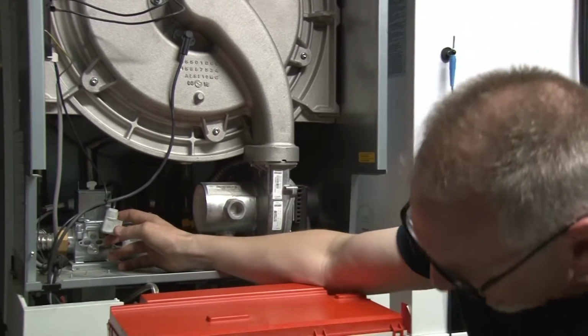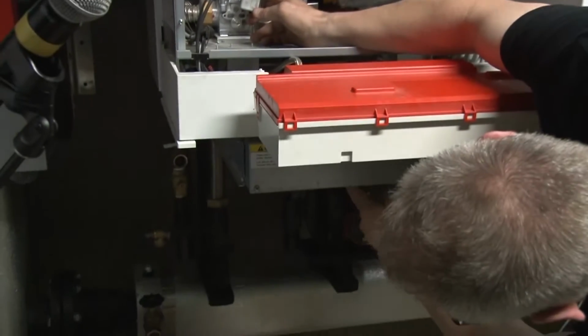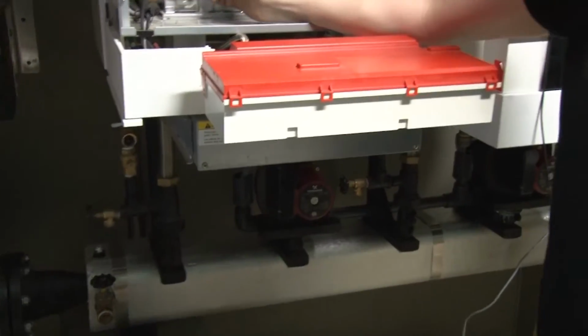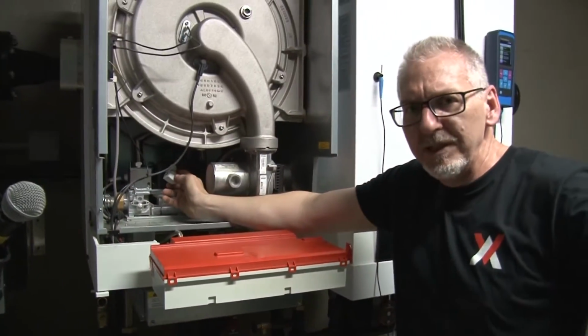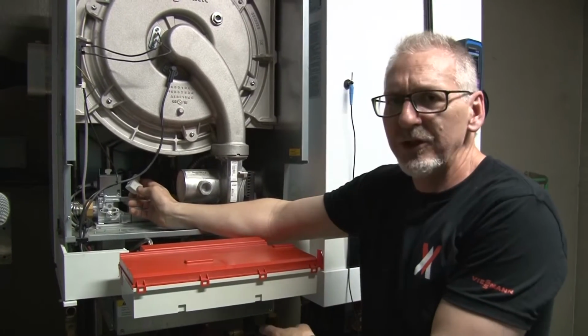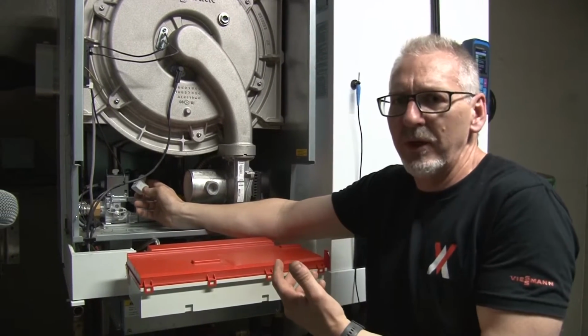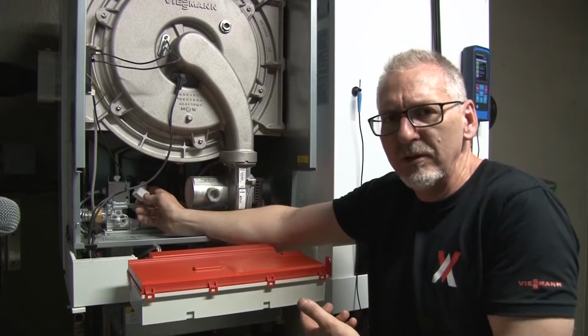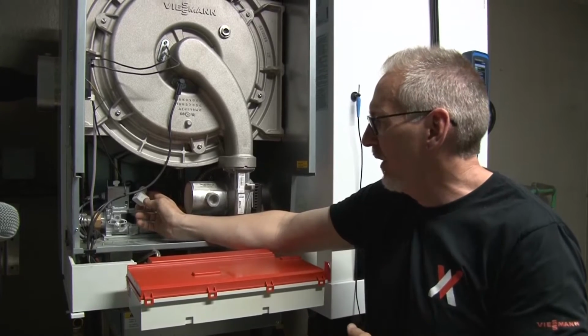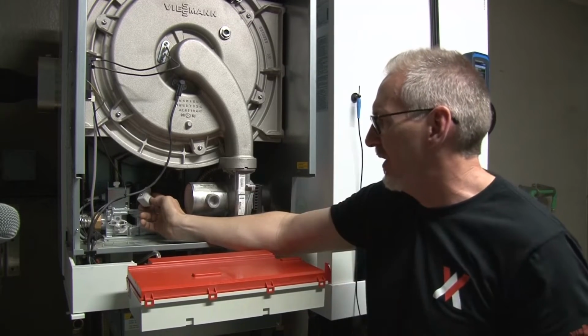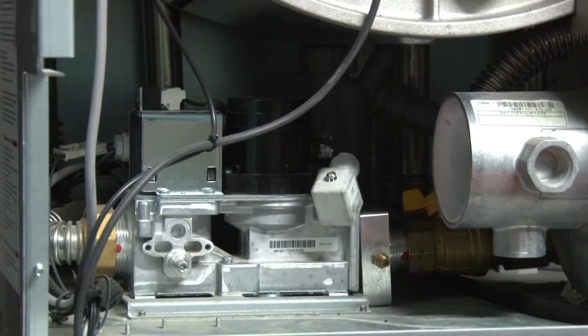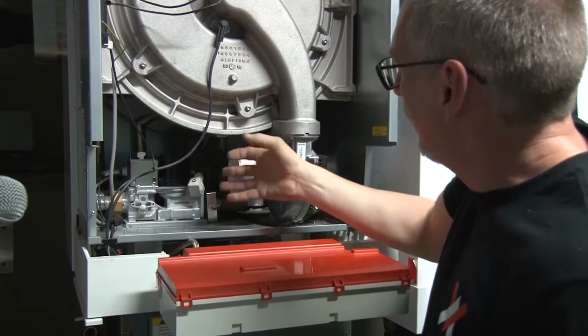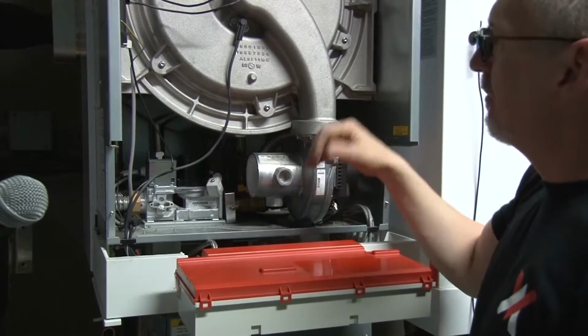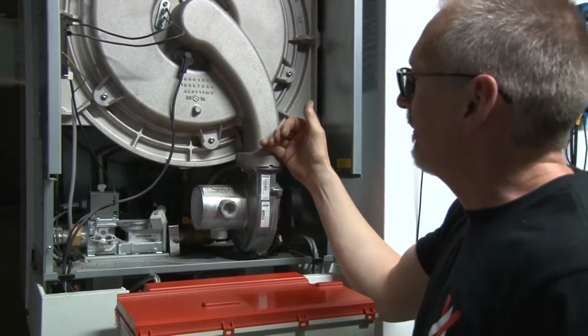You might also have a manual low gas pressure switch on your gas line here, depending on where you're at. I know a lot of areas where I'm from in BC that we have a manual switch on that side. The safety authority likes to have something that it manually locks out if there's low gas, so they'll have that. This is not, this is an automatic reset switch. So now that I've got that unplugged, I can freely remove the gas train here out of the boiler, the portion that I need for service.